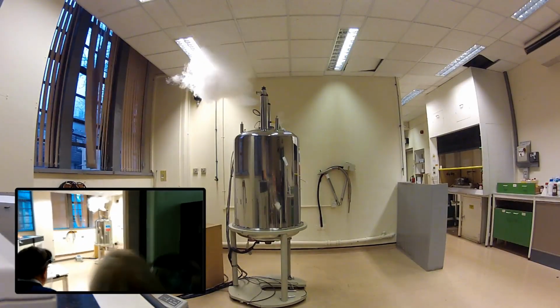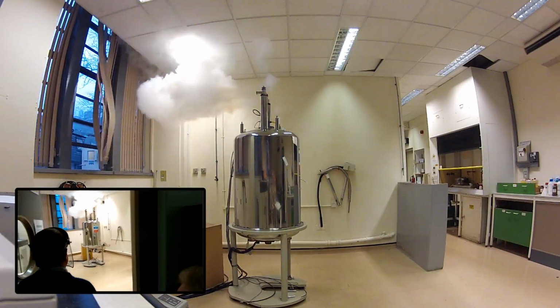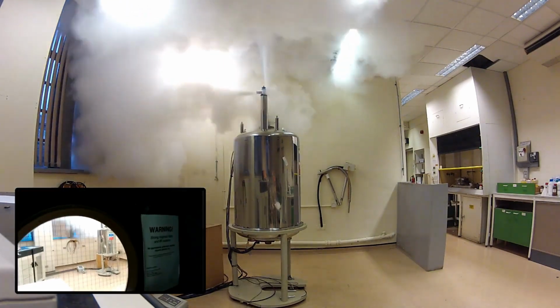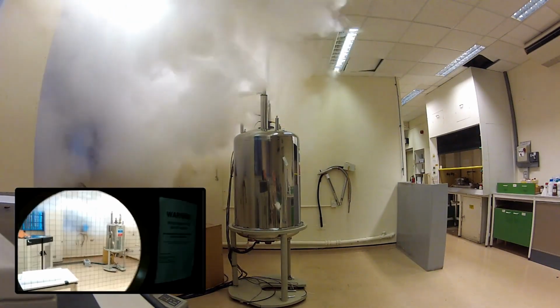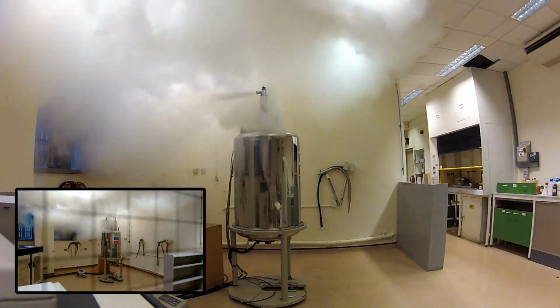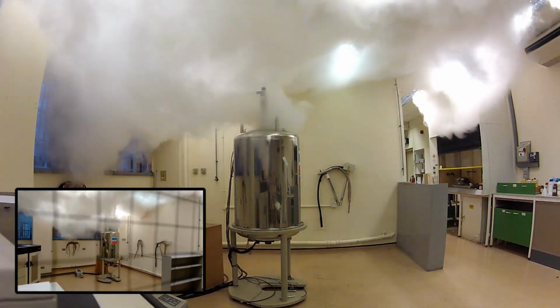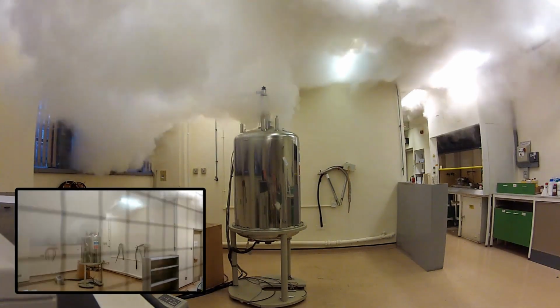The NMR magnets need to be kept at extremely low temperatures to maintain their superconductive properties. Helium is used because it has the lowest boiling point of any material at 4.2 Kelvin. The magnet must be submerged in liquid helium without fail at all times, otherwise superconductivity will be lost. This can damage the magnet in addition to the fact that recharging a magnet is very expensive. Therefore, it is imperative to have a reliable and affordable supply of liquid helium.